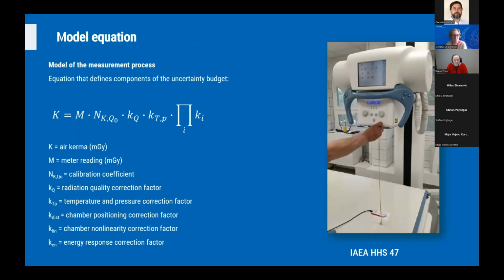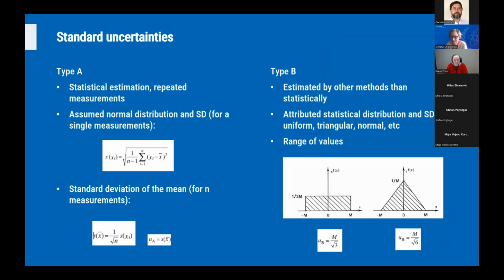In the case of dosimetry, it is in principle the dosimetry formalism, as in this example that you can see on this slide related to air kerma, which is a product of the meter reading or measurement results corrected for calibration coefficients and a number of correction factors related to the radiation quality, environmental conditions, and other influencing quantities related to the properties of the setup and instrument itself. The standard uncertainties, again, this is something that we know very well, just to remind ourselves, can be classified as type A and B.